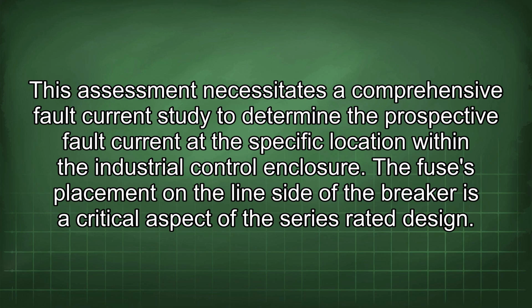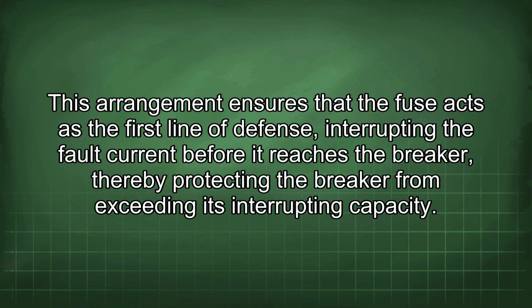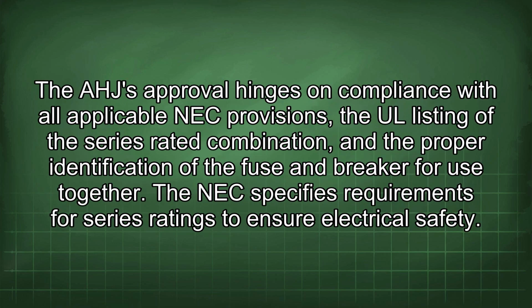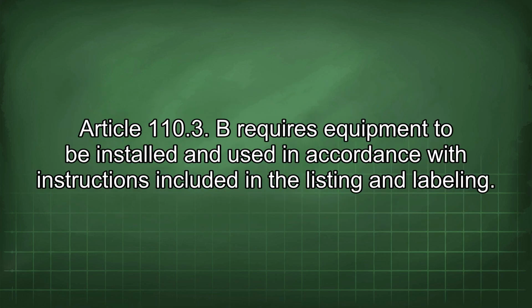The fuse's placement on the line side of the breaker is a critical aspect of the series-rated design. This arrangement ensures that the fuse acts as the first line of defense, interrupting the fault current before it reaches the breaker, thereby protecting the breaker from exceeding its interrupting capacity. The AHJ approval hinges on compliance with all applicable NEC provisions, the UL listing of the series-rated combination, and the proper identification of the fuse and breaker for use together. The NEC specifies requirements for series ratings to ensure electrical safety. Article 110.3 B requires equipment to be installed and used in accordance with instructions included in a listing and labeling.